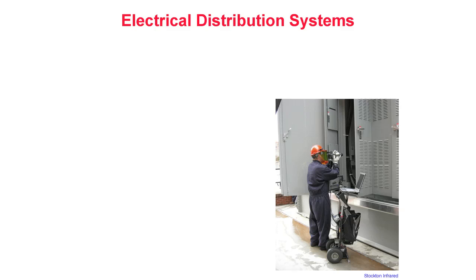Electrical distribution systems. When it comes to reliability, few systems are more important to facility operations than the electrical system. Unscheduled downtime can be costly by interrupting production and idling workers while repairs are made. In some cases, electrical failures can cause catastrophic failures, including fires. Fortunately, infrared thermography can be utilized to detect incipient or certain types of acute failures within an operating electrical system. The theory behind this application is simple. Electrical current flowing through conductors and devices generates heat. Many electrical defects are accompanied by a rise in temperature. In some cases, this increase in operating temperature may be present for up to several weeks prior to a failure.